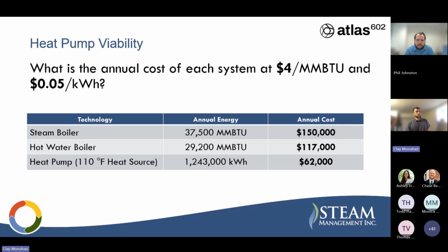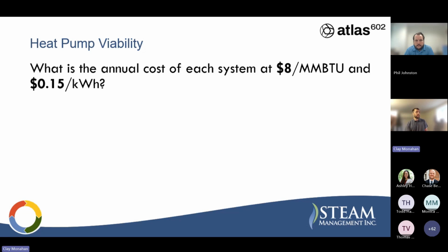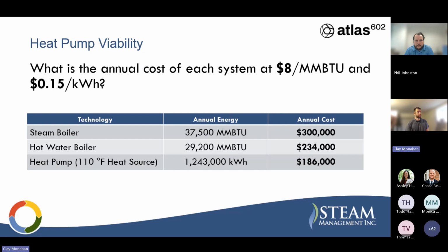Their steam boiler cost goes to $150,000, 117, and then $62,000 on the heat pump. So that's going to be $88,000 a year saved. Obviously, if your utilities just cost less, your savings are going to be less. And then if we're out somewhere like the Northeast, where we have more expensive gas and more expensive electricity, the steam boiler is going to cost significantly more. The heat pump's going to cost more, but the delta is going to be increased to 115,000. So Phil's going to get into spark spread, and that's basically the introduction to this concept and how that affects it. But your energy prices obviously have a big effect on the viability of the project.